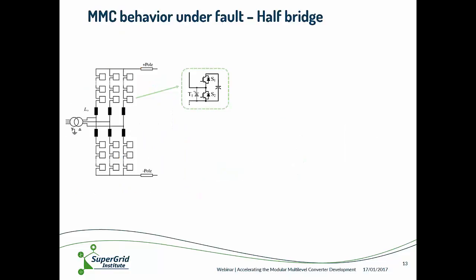The converter is not always under control, especially when a half-bridge MMC is submitted to a fault. So what happens when there is a fault? Under a fault, the MMC capacitor current will rapidly increase because the capacitor modules start to discharge into the fault.